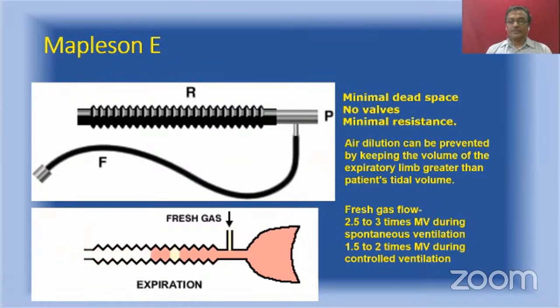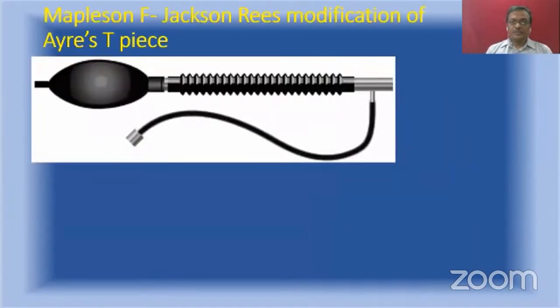And the fresh gas flow requirement for spontaneous breathing is 2.5 to 3 times minute ventilation. And for controlled ventilation, it is around 1.5 to 2 times minute ventilation. That means the fresh gas flow requirement is still high. Now we move on to Mapleson F circuit, which is actually called the Jackson-Rees modification of Ayre's T-piece. This circuit was introduced by Jackson-Rees and included in the Mapleson classification at a later date by Willis et al. The advantage of the Jackson-Rees modification over the T-piece is that there is a reservoir bag. You can see the reservoir bag with a tail which has a hole. So because of the reservoir bag, you can see the respiratory movements and also you can control the ventilation.